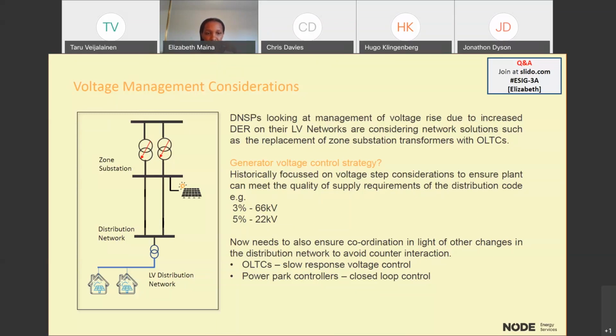So some of the things we're looking at and thinking about as we look at projects connecting on that distribution level is whether, for example, the DNSP is looking at any replacements in the coming future that may affect what needs to be designed as far as a voltage control strategy, to ensure that we can meet the quality of supply aspects, but also ensure that we're not having any negative counter interactions that may have other effects, as well as affect what the DNSP is trying to achieve in terms of voltage management. When you've got another controller that comes in there that's doing something opposite to what the DNSP is looking at, we ensure that those are coordinated.